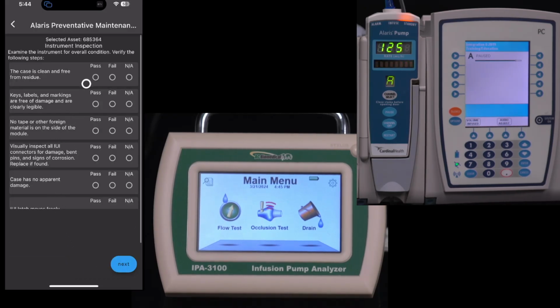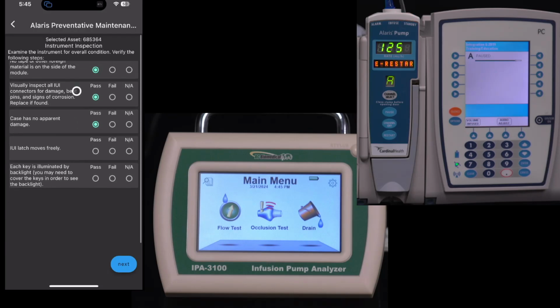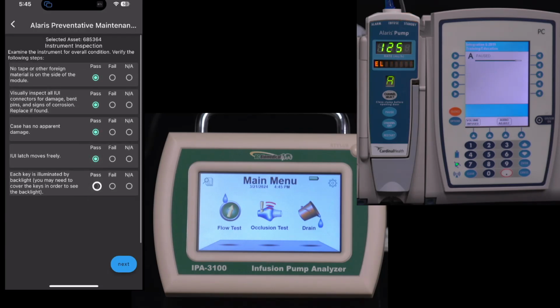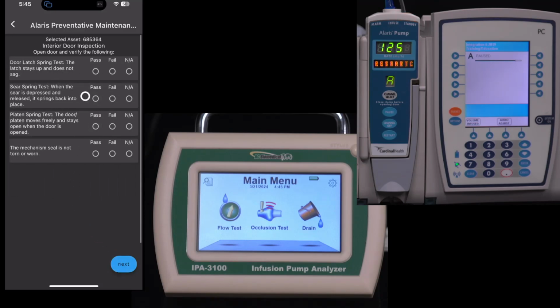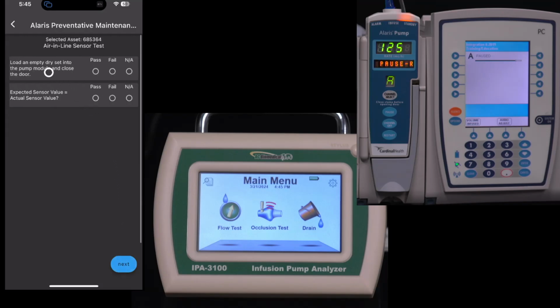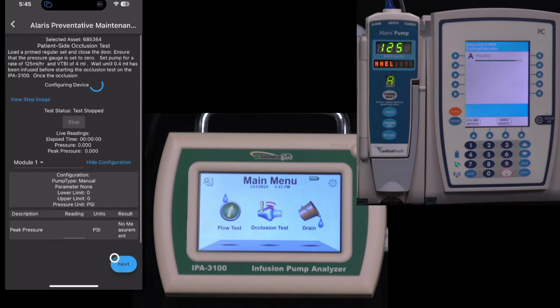And just like the test sequence in the service manual, we have a lot of inspections to do, right? We have to check the case. We have to check all the keys and make sure there aren't any foreign objects. So this is the same checklist that we would see in the service manual. And we'll go through that step. And the next step, inspect the door latch, make sure the silence button works. That's the most important one for me. So we'll go through and do all these physical manual inspections, and we'll load an empty set into the pump. Well, we just filled this one, so we'll just pretend like we had an empty set, and we did that. All of our manual inspections.